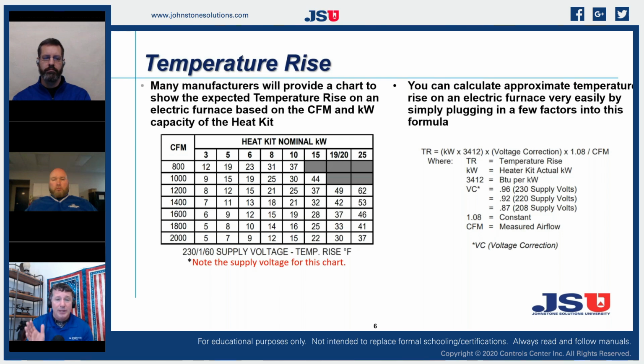And we know that when our temperature rise gets high, especially above 50 degrees, we're going to start burning up elements on an electric furnace. So the rule of thumb on a high efficiency furnace is 35 to 55 degrees, in that ballpark, right? So I can safely say that most manufacturers are going to be in that range on a gas furnace. I have seen some go higher, but not typically.